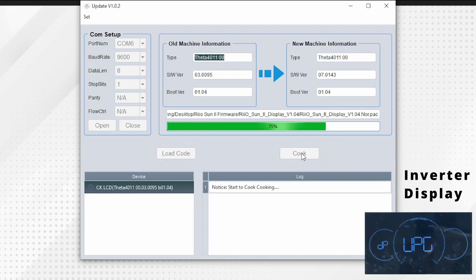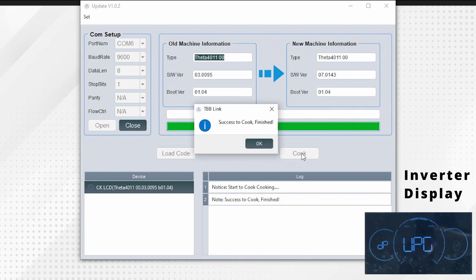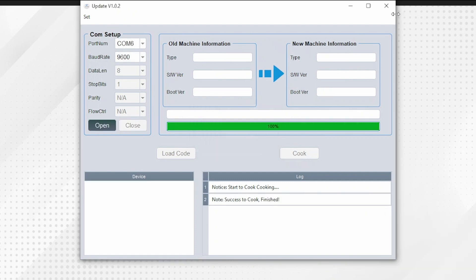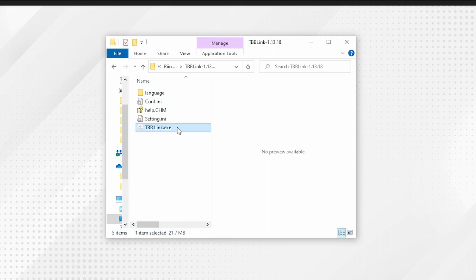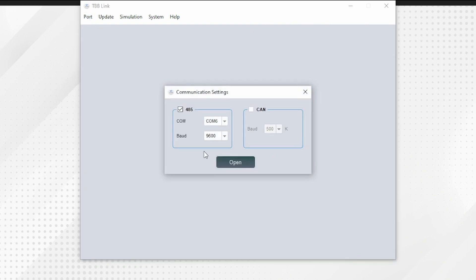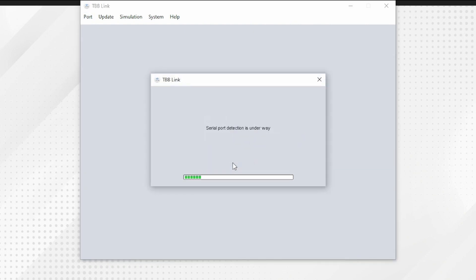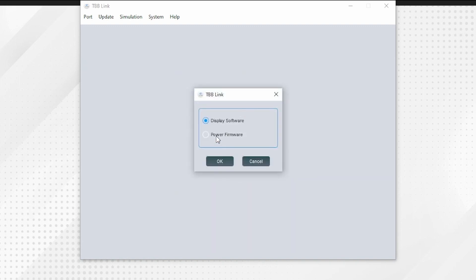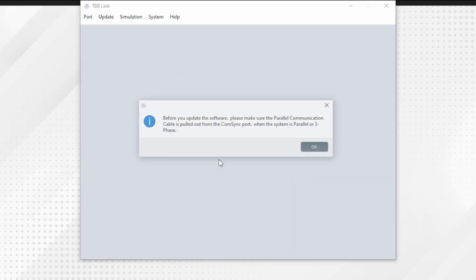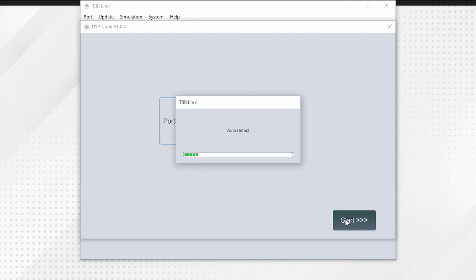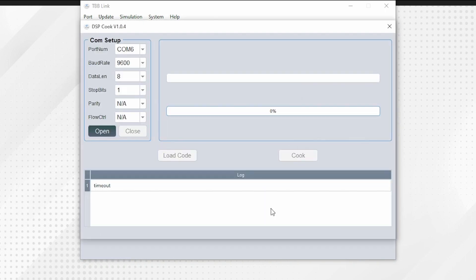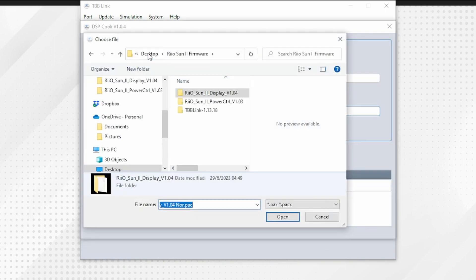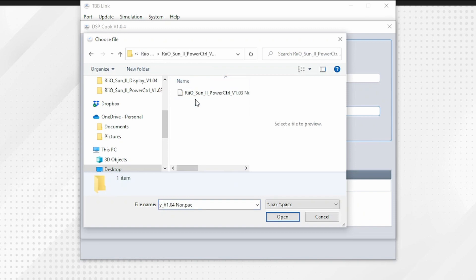Once finished, you can exit the program. Reopen the TBB software to update the power control firmware. It will ask you to select the equipment you are connected to—choose inverter. On the menu screen, choose update, choose the power firmware option. The parallel or three-phase warning will be displayed. The comm port will then be displayed—it will auto-detect, and from there you can load the power control firmware.